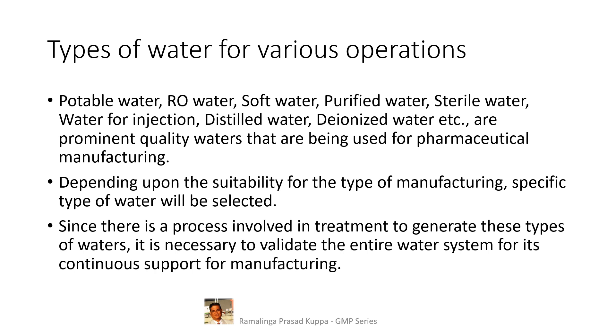Since there is a process involved in treating water to generate these types of waters, it is necessary to validate the entire water system for its continuous support to manufacturing. Any pharmaceutical process equipment must be qualified, and the process carried out in that equipment must be validated. All critical equipment for water generation and distribution must be qualified to meet design, installation, operation, and performance requirements of the treatment process. A detailed protocol is necessary to capture all critical parameters, and a detailed report after evaluating the data statistically would take you to the best water treatment system.